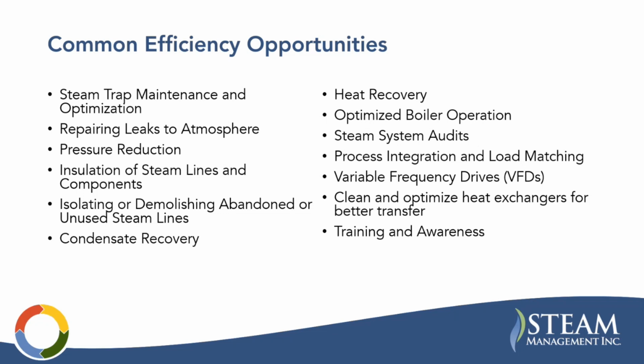Next is repairing leaks to atmosphere. Again, you are just wasting steam, so obviously those need to be addressed. Pressure reduction is a good opportunity. If you can reduce the pressure in your steam system, you basically reduce your energy losses. If you can do the whole system or just a section of the system, any losses through your pipe walls, like thermal losses, are reduced because now you're at a lower temperature. So there's lower differential temperature between the pipe and the ambient. You're reducing losses through traps because you have less pressure to push that steam through the trap. You're reducing losses in leaks, and it basically just reduces energy loss across the board. If you can actually do it in your boiler, then you're now reducing your boiler feed water pump energy requirements and your gas use, because you're now requiring less energy to get up to a lower temperature set point or pressure set point.